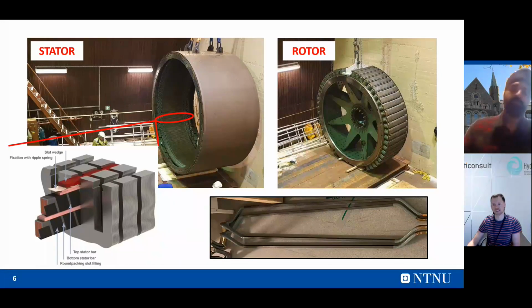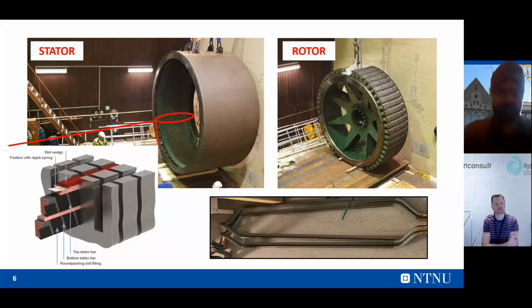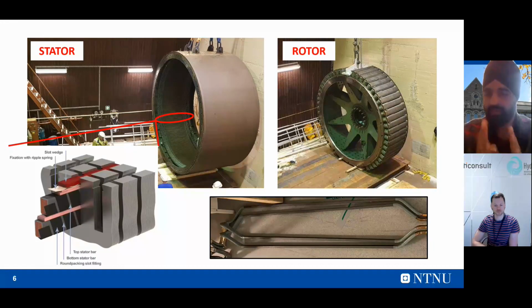From that site, I observed that this is generally because of the placement of the stator bars inside the slots. At the end points, we usually find that the gap between the nearby bars is quite small, which can ultimately cause bar-to-bar breakdown at the end points, because these are the points where the electric potential is quite high compared to the center part. The gap is very small there, which causes bar-to-bar discharges and ultimately leads to breakdown of the insulation.